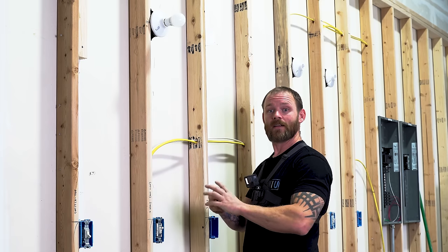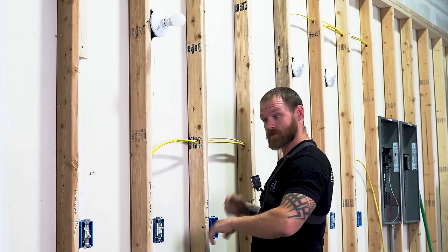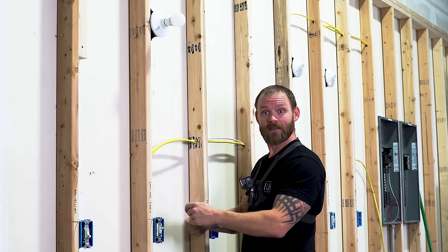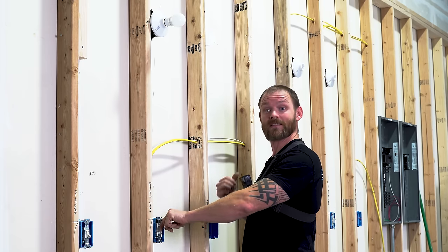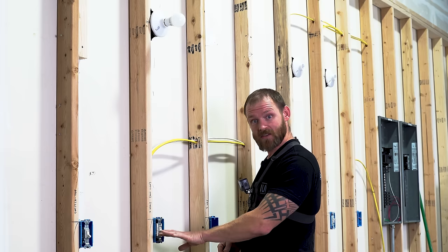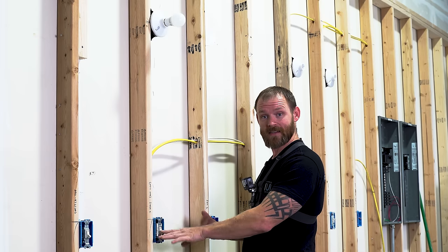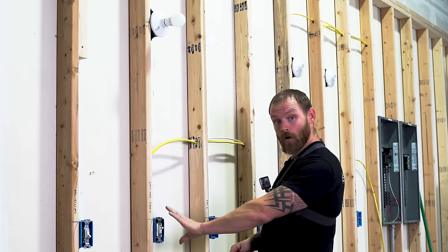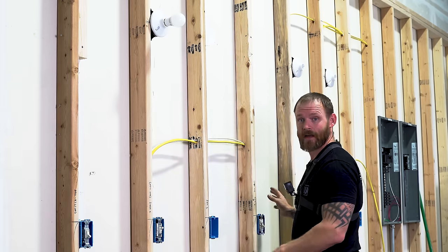And then now they're instead of passing the hot through the box, they're using the device. Mistakingly, they're hooking the hot up to the device. So the connection for the rest of the circuit only happens once you flip the switch into a certain state. When you flip it back, there's no longer a connection through to the rest of the circuit.